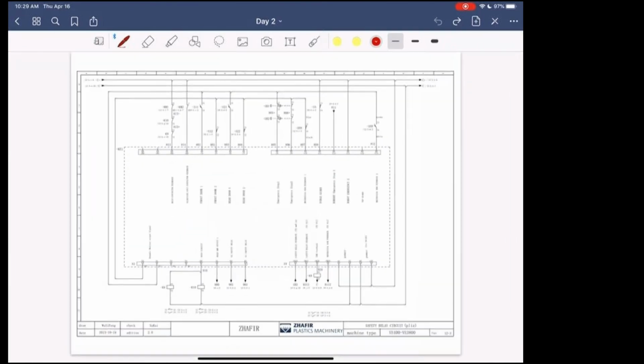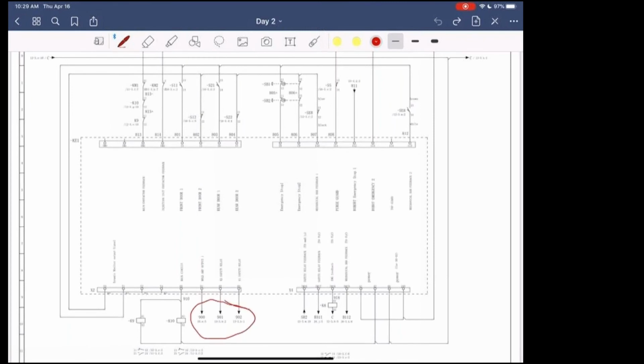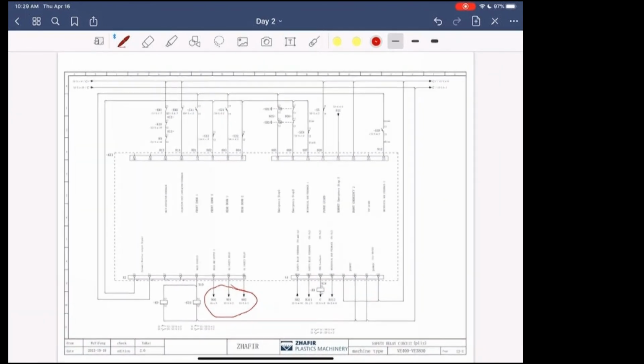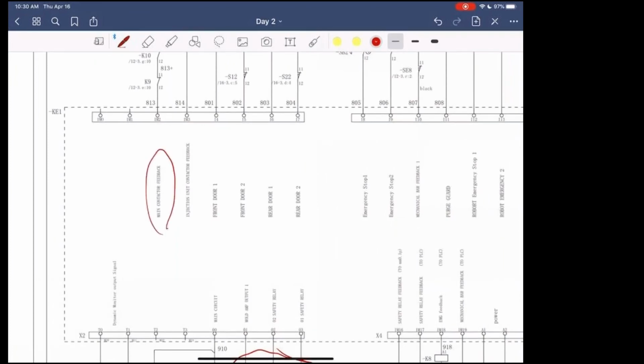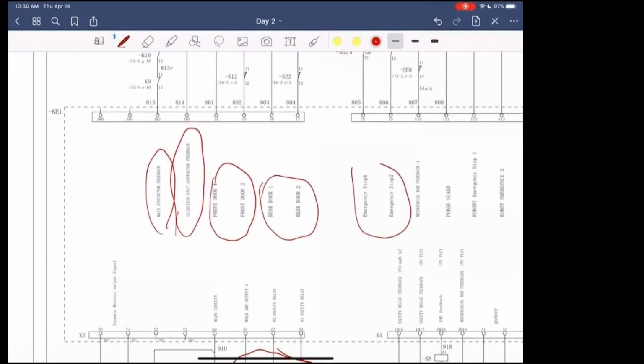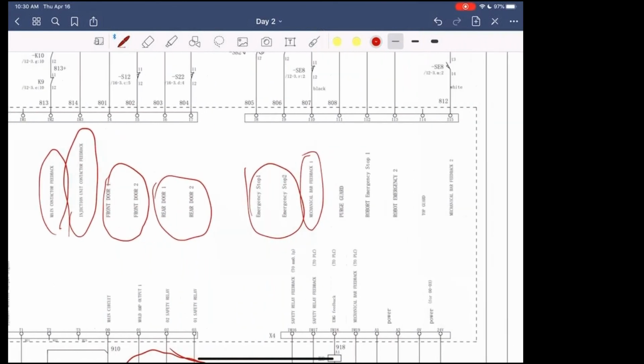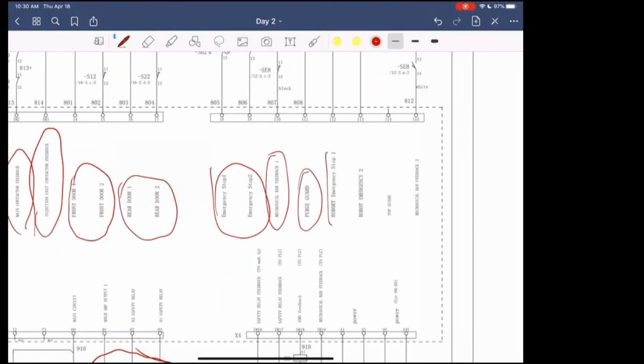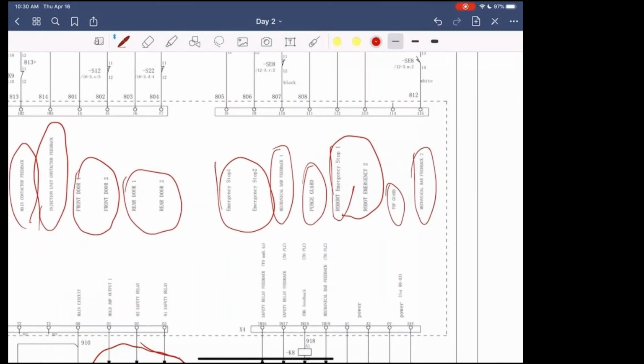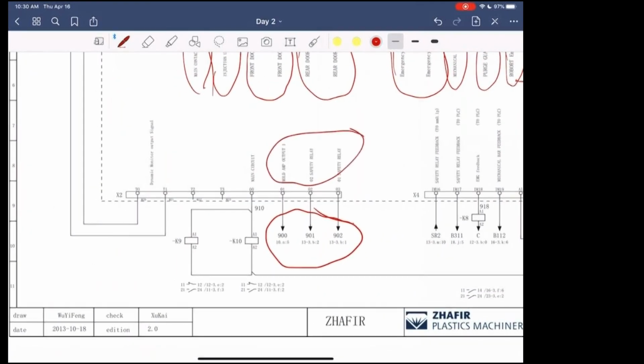All right. This guy here is a safety relay circuit. Again, we covered this yesterday. This is the pills. And these are your 900, 901, 902s, which is your safety relays. So you have your main contactor feedback, injection unit contactor feedback, your front doors, your rear doors, your e-stops, your mechanical bar, which is your drop bar, purge guard, robot emergency stop 1 and 2, top guard, another drop bar, and then again you have all your outputs.